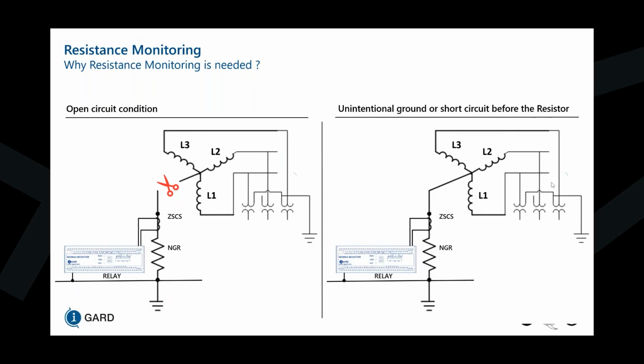And in addition to that, we also have our short circuit scenario where our system becomes solidly grounded and our CT can potentially be bypassed here. In this case, we won't know that the system is solidly grounded. The protection scheme downstream may not be set properly for a solidly grounded configuration, and we're no longer protecting the system from high levels of fault current, which could lead to arc flashes or arc blasts.